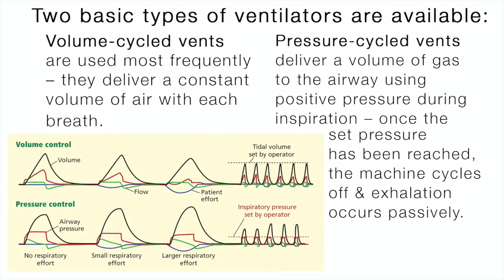There are two basic types of ventilators available: pressure-cycled ventilators and volume-cycled ventilators. Volume-cycled ventilators are used most frequently; they deliver a constant volume of air with each breath. Pressure-cycled ventilators deliver a volume of gas to the airway using positive pressure during inspiration. Once the set pressure has been reached, the machine cycles off and exhalation occurs passively. Our focus will be on volume-cycled ventilators, since they are used more frequently.